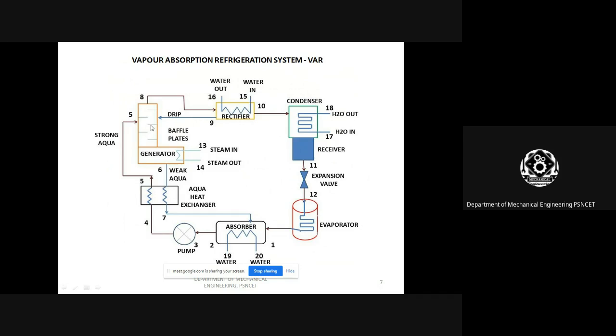In this generator, before going to the condenser, some of the weak ammonia again goes to the heat exchanger and then it is passed on to the absorber. In the absorber it absorbs the weak ammonia solution, and once again it is pumped through the heat exchanger as a strong ammonia solution to the generator. So this process replaces the compressor in the VCR system. All other things are the same.